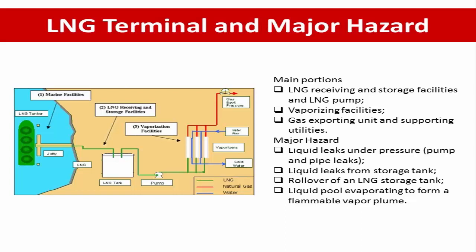Major hazards associated with the LNG terminal. During the engineering phase, loss of containment of LNG to the surrounding is the most critical consequence. From the LNG storage tank, when LNG is poured on the ground, a small quantity of liquid can be converted to a large volume of gas when spillage occurs. One volume of liquid will produce approximately 600 volumes of gas at ambient conditions. Initially, the gas produced by evaporation is at nearly the same temperature as the LNG and is denser than the ambient air, forming a vapor cloud which could cause a vapor cloud explosion, or VCE, resulting in multiple fatalities in the area.